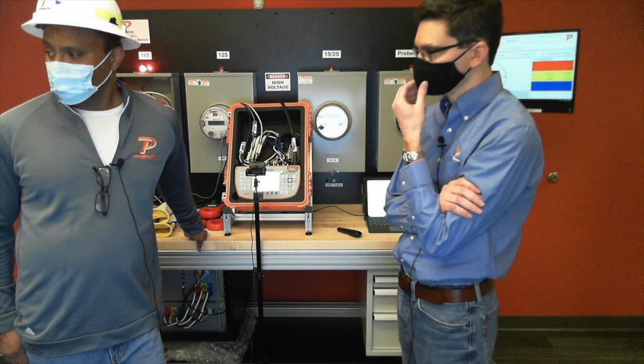Jim B says, how would a 15S meter if the neutral on the pole was broken? You wouldn't have that high leg, right? No high leg. Yeah, you'd probably show nothing on C phase. You'd still get your phase-to-phase voltages for VAB, your 240, but your high leg voltage would be... you'd have nothing on your high leg. That's a good question too—it'd be floating, I guess you'd say, wouldn't it? Your vector diagram would be flip-flopping all over the place. That's true, because there's no reference phase.